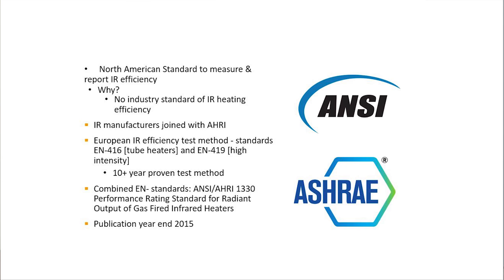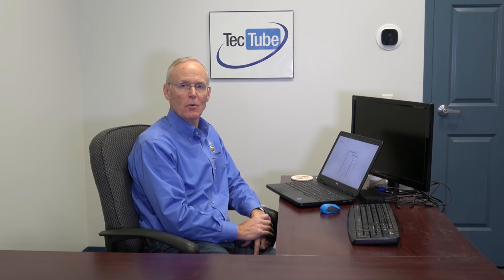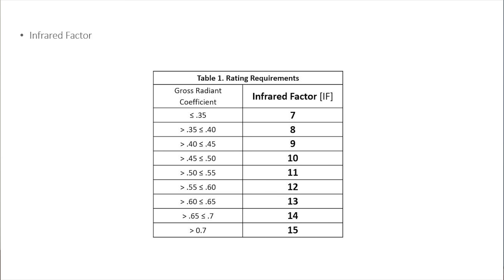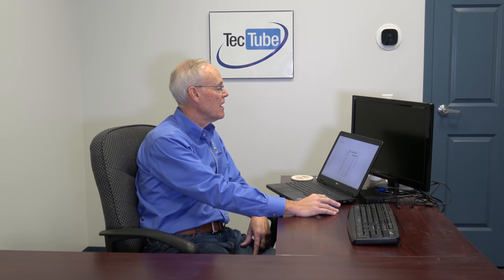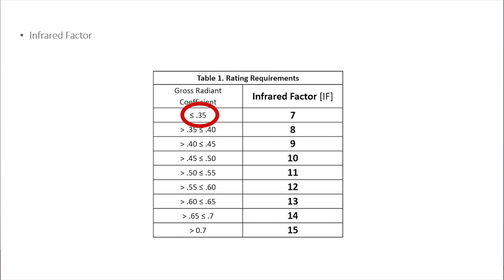Every manufacturer should have this standard. The way it works is it sets up a kind of SEER — if you want to call it that — in residential applications. It takes this gross radiant coefficient, established by setting up a grid pattern and monitoring the radiant temperature off of each four-inch by four-inch grid, and comes up with a gross radiant coefficient. Anything under 35 percent — the industry standard — gives an infrared factor of 7. Anything above 70 percent gives an infrared factor of 15, and that comes into play with the next slide.